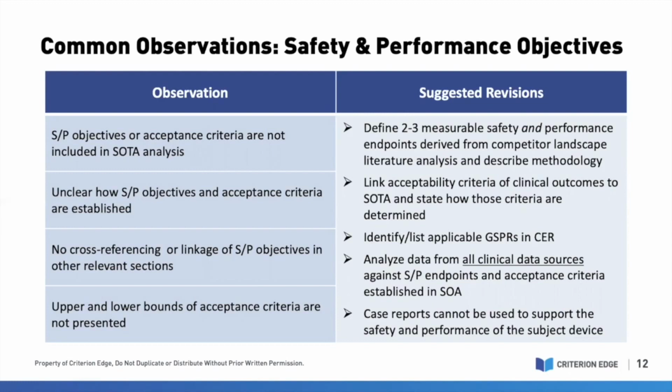Again, it's critical to analyze all clinical data sources against the endpoints and acceptance criteria. Lastly, it's important to note that information derived from published clinical case reports is considered a very low level of evidence and thus cannot be analyzed against established safety and performance acceptance criteria.